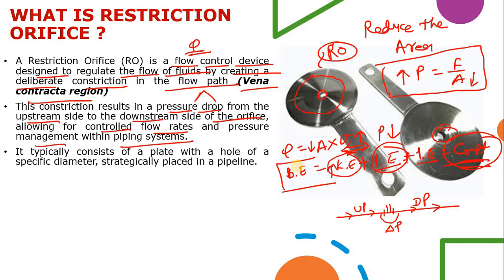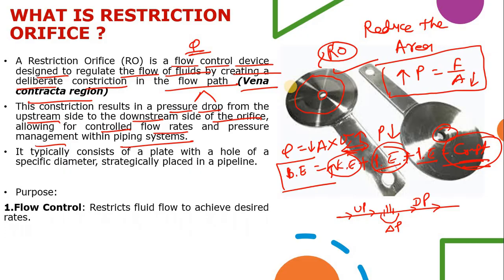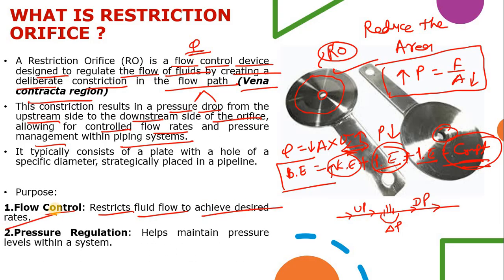The restriction orifice typically consists of a plate with a hole of a specific diameter strategically placed in a pipeline. The hole diameter is based on process parameters and process conditions. Its two main purposes are: first, flow control — it restricts fluid flow to achieve desired flow rates; and second, pressure regulation — it helps maintain pressure levels within the system by creating a delta P between upstream and downstream.